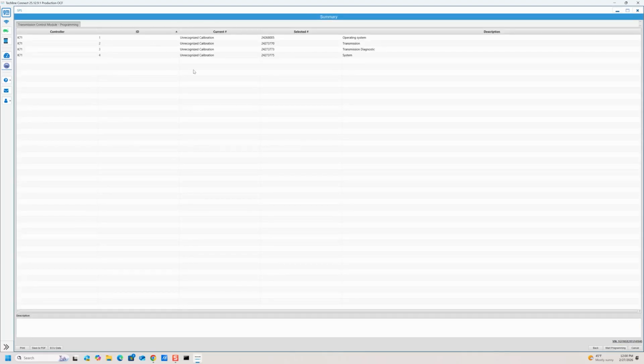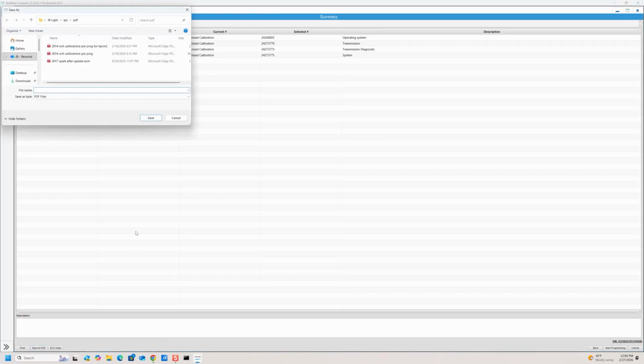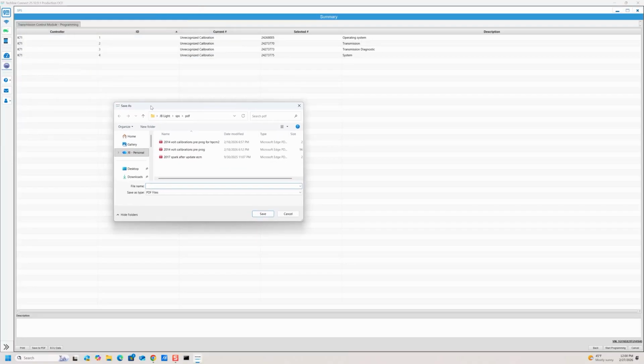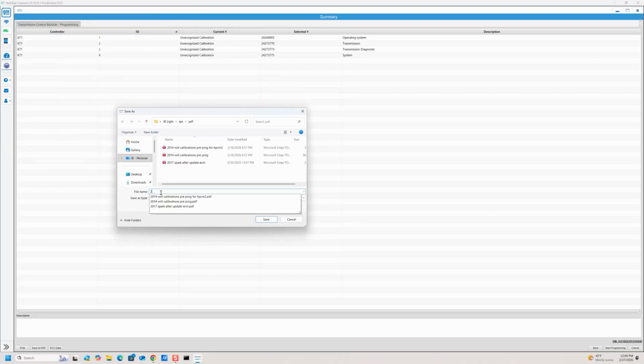And now you can see there's no calibration recognized in the module, indicating it's blank. And it shows we have selected the 3 newest calibrations there. We're going to make a little PDF here for documentation, just showing the before we programmed it. That way we have this in case there is any question as to whether or not we did the proper programming. So here's our pre-programming PDF, and we'll save it and we'll show you what that looks like.